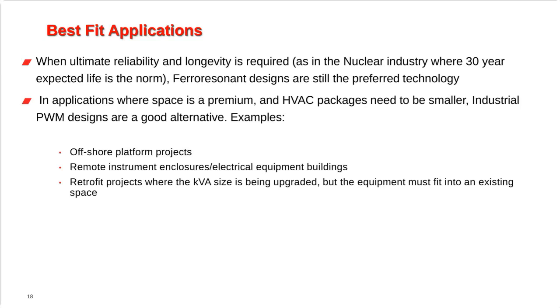Although our DPP is now Nuclear 1E certified, so our PWM technology can now be installed inside of safety-related nuclear applications, because it's such a tried and trusted technology, the ferro-resonant system is still the norm. But in applications where space is at a premium and HVAC packages need to be smaller, the industrial PWM designs are a good alternative. Examples for that are offshore platforms, remote instrument enclosures or RIE buildings, or retrofit projects where the kVA size needs to be bigger, but the equipment must still fit into an existing space. So, for example, for a 30 kVA ferro-resonant, you could probably quite easily replace that with a 50 kVA DPP, but you could not replace it with a 50 kVA ferro-resonant system because it would be physically bigger.